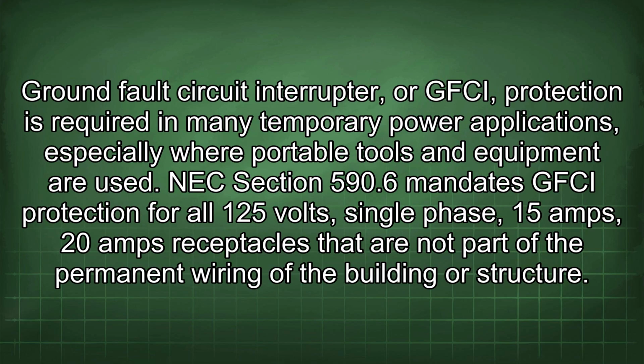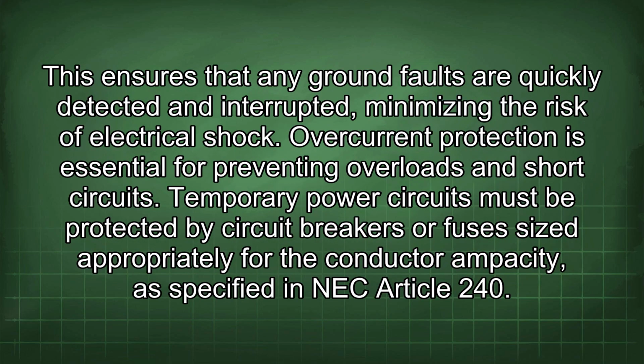Ground fault circuit interrupter, or GFCI, protection is required in many temporary power applications, especially where portable tools and equipment are used. NEC Section 590.6 mandates GFCI protection for all 125 volt, single-phase, 15 amp and 20 amp receptacles that are not part of the permanent wiring of the building or structure. This ensures that any ground faults are quickly detected and interrupted, minimizing the risk of electrical shock.